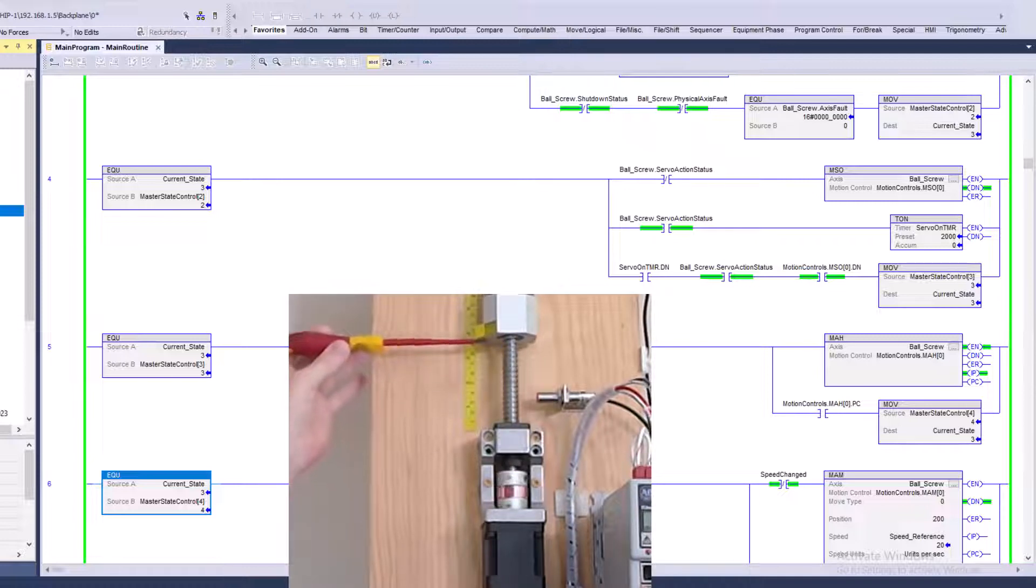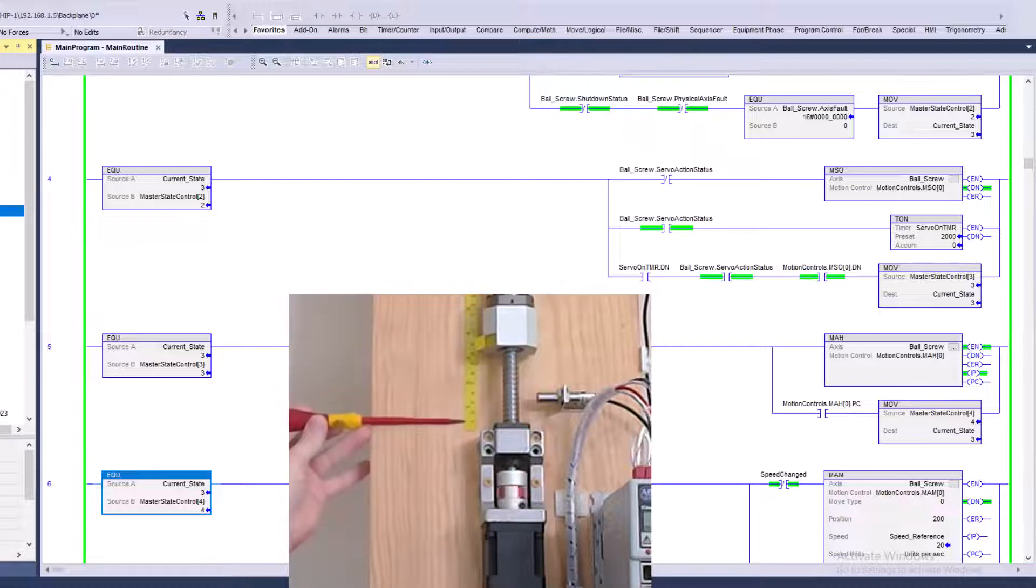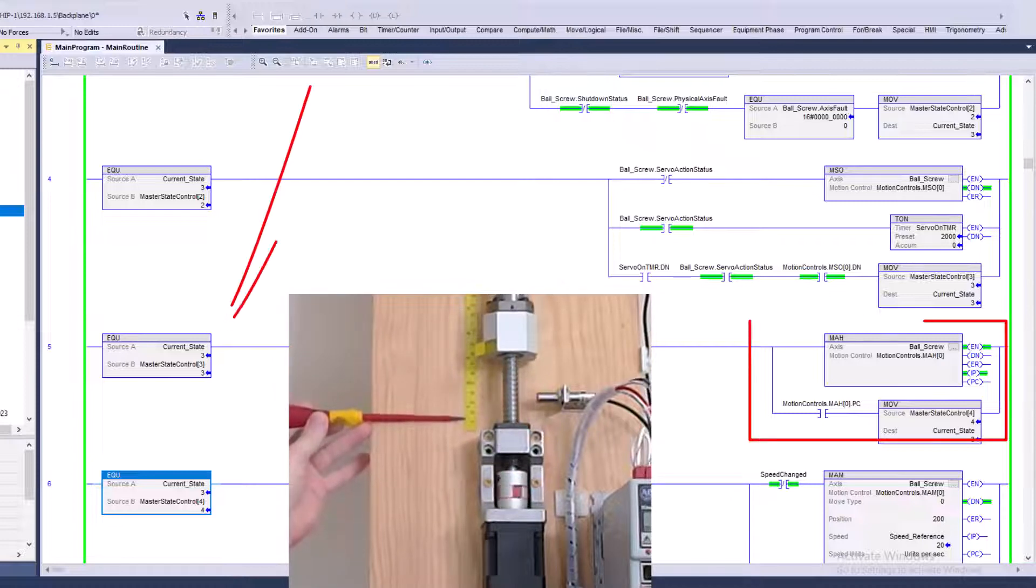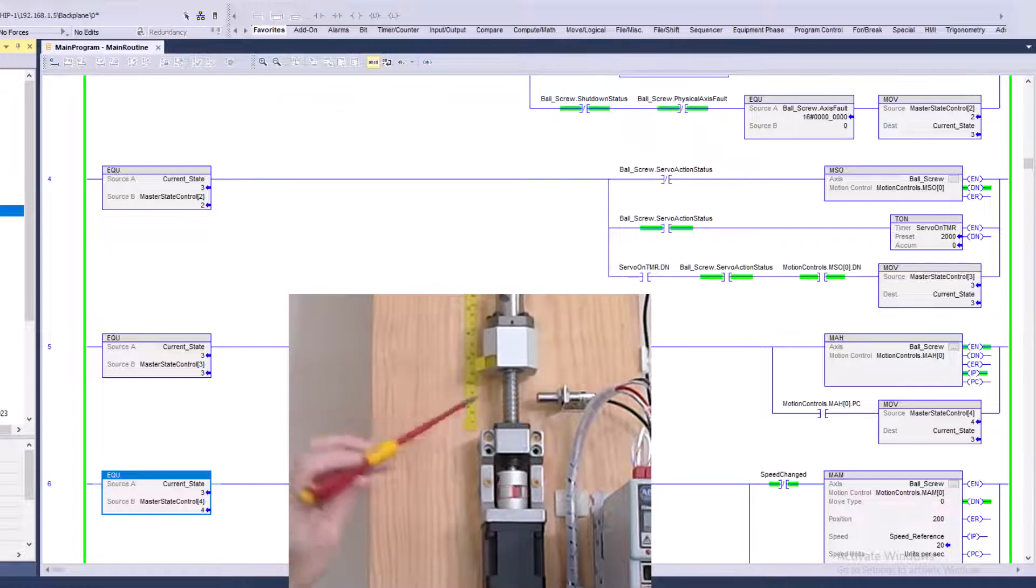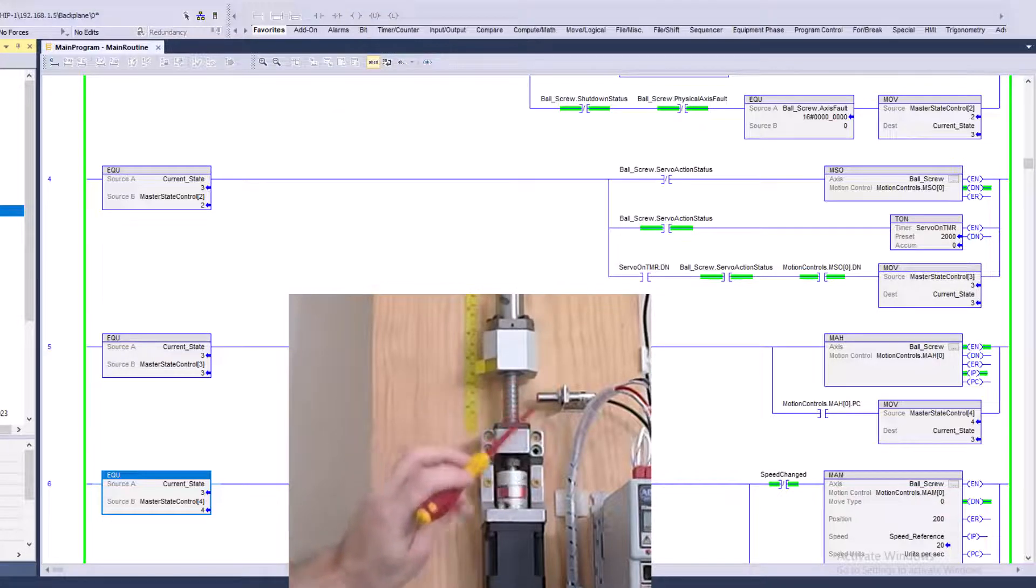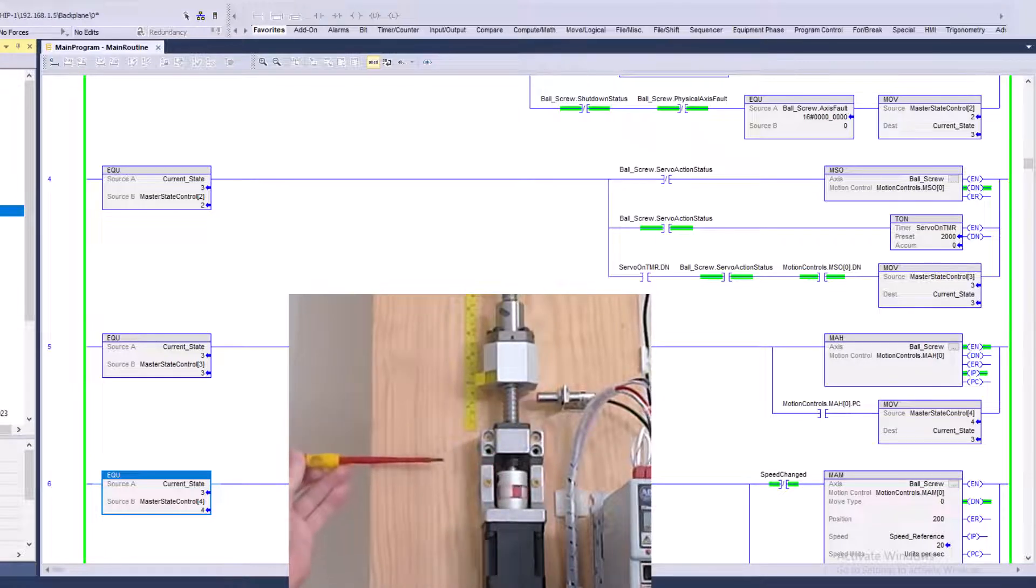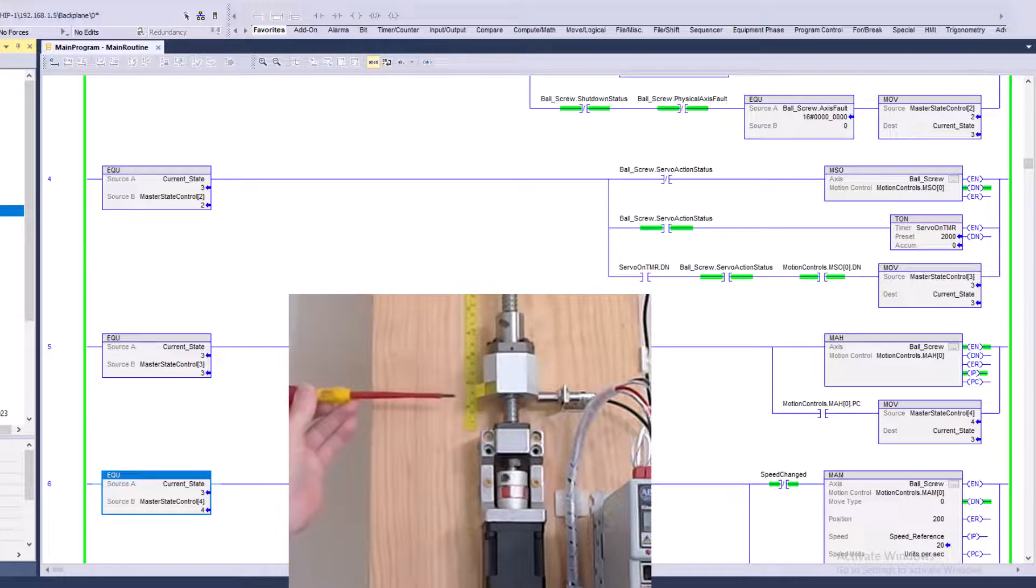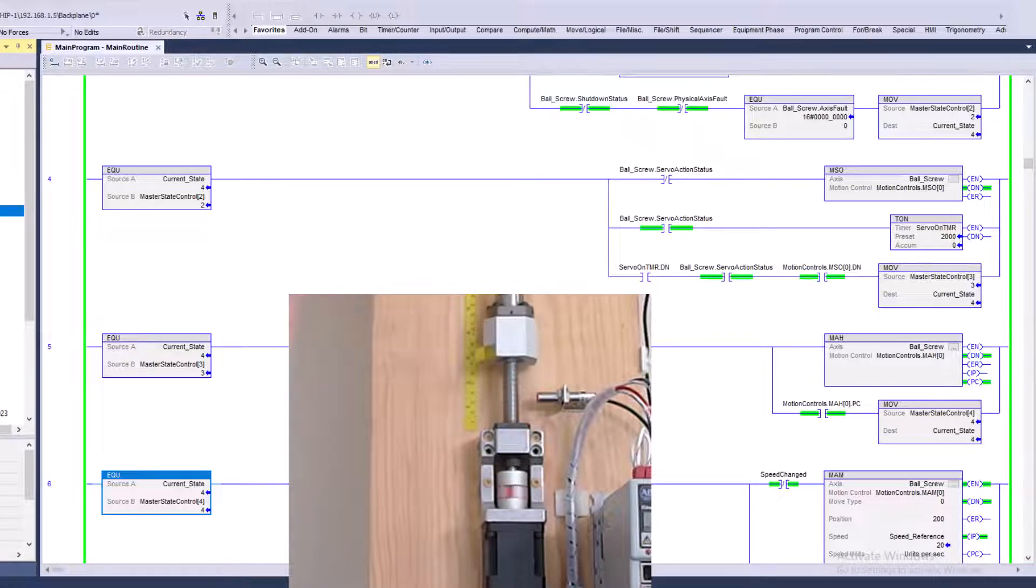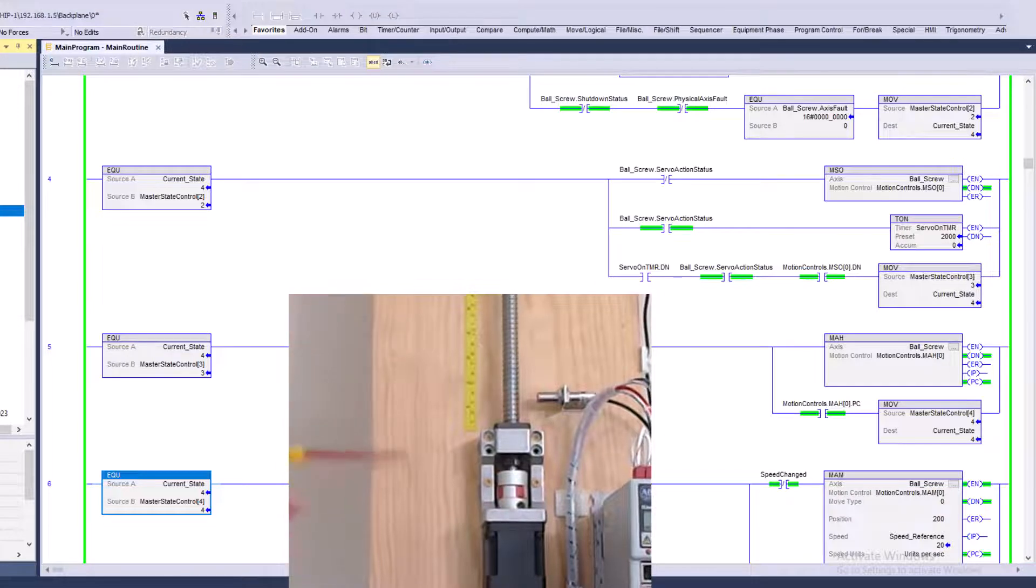Now, if you note this bottom piece right here, which is what we've been referencing as our position is going to be down here and it's going to be about 28. And that's when this prox will measure, will actually get in and make contact. It will make contact closure. So as soon as it happens, it goes ahead and skips to the next step right here or the next state we have in our state machine. And then it continues on back to its process.